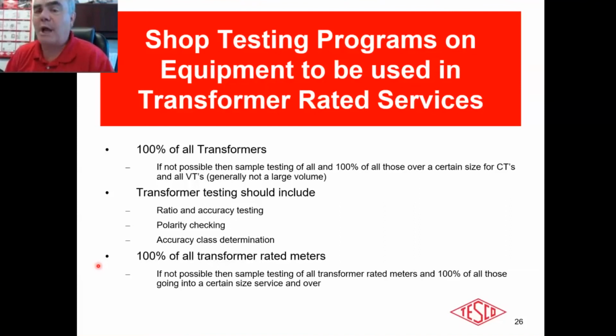However, if you're putting in, I don't know how many of you use 2000 to 5s, 4000 to 5s. If you are putting in a large transformer, spend the time to put that cable as best you can, have that cable go right through the center of that service. Not so problematic at 2000 to 5. It really starts to show up once you get to 4, 5, and 6000 to 5. So if, and only if, most utilities, they're not doing it that way. But if you're using those and they are out there, make sure that you take the time to put those cables through the center of the services. So thank you for that, Jim.